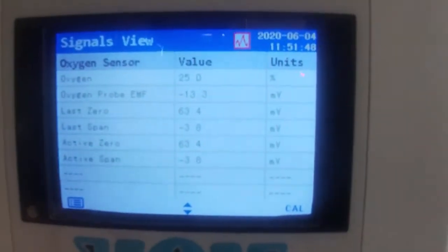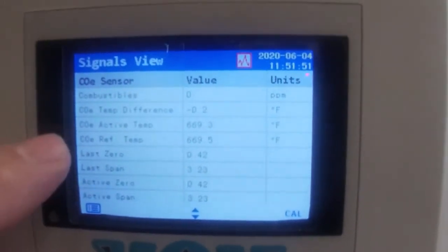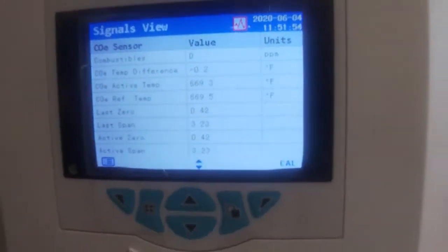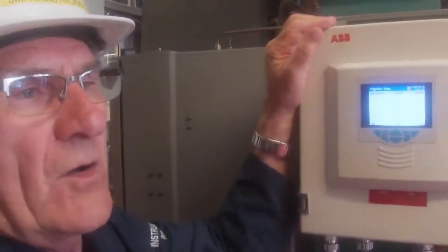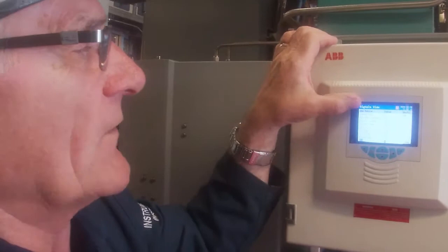This is for the oxygen sensor page. And then on my COE, COE means carbon monoxide equivalent. So we calibrated with carbon monoxide. If it was seeing hydrogen coming through, it would actually give us a higher value because it's going to get more heat off of that hydrogen burning, and it would be the equivalent of so many parts per million of carbon monoxide. It would be a much larger number. So that's what the E means. It's carbon monoxide equivalent, basically saying this thing is calibrated for carbon monoxide. And if you've got some other gases, well, it's not going to be exactly the ppm that you think it is.